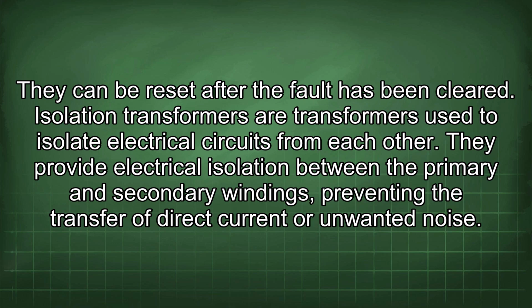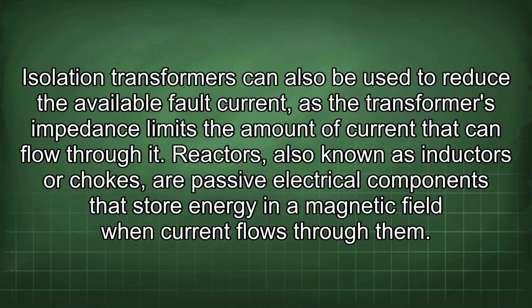Isolation transformers are transformers used to isolate electrical circuits from each other. They provide electrical isolation between the primary and secondary windings, preventing the transfer of direct current or unwanted noise. Isolation transformers can also be used to reduce the available fault current, as the transformer's impedance limits the amount of current that can flow through it.